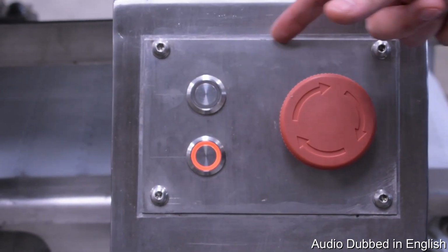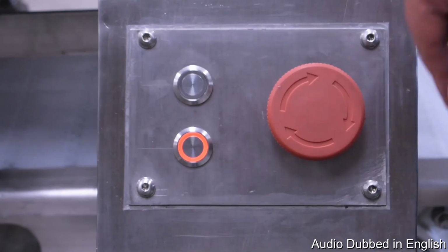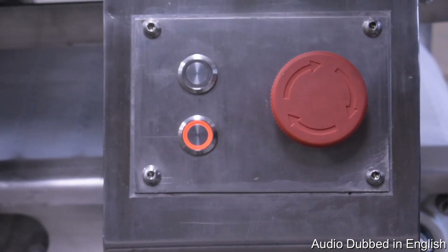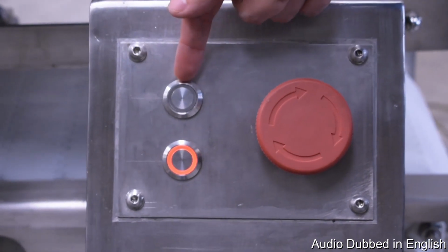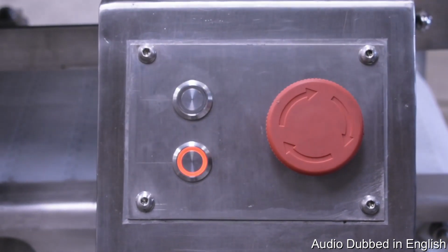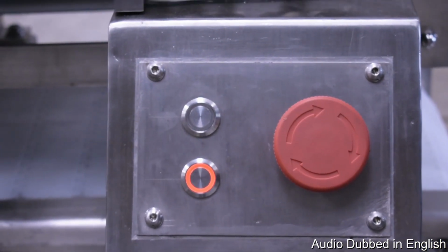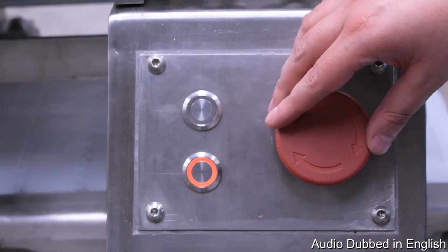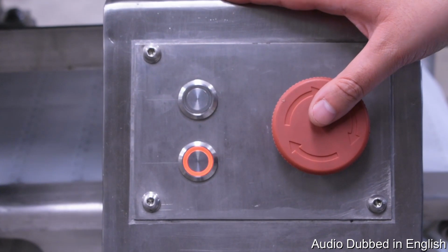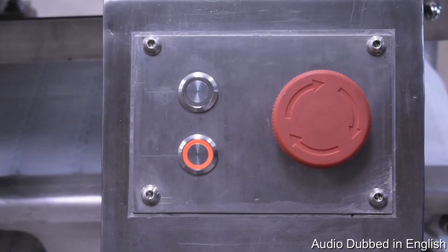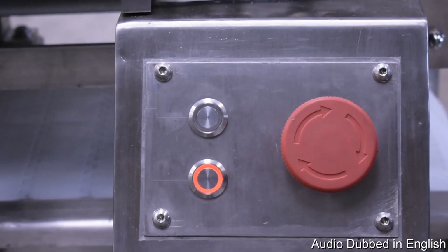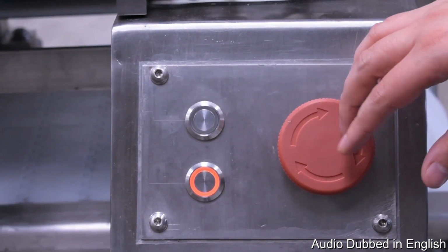So if I wish to control both drives at the same time, what I did was to connect this same input to both of the inputs for our drives, which means that this is a parallel connection. This is only if we wish to control two or more drives through one only button.